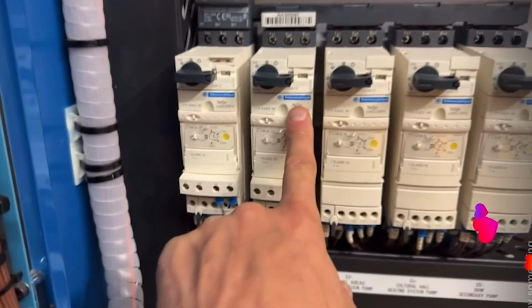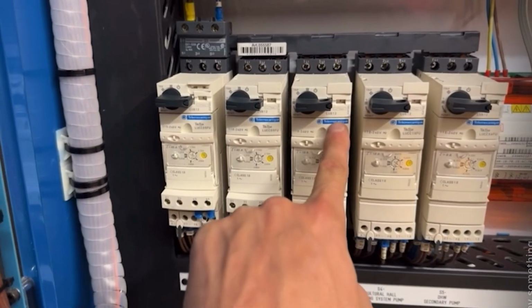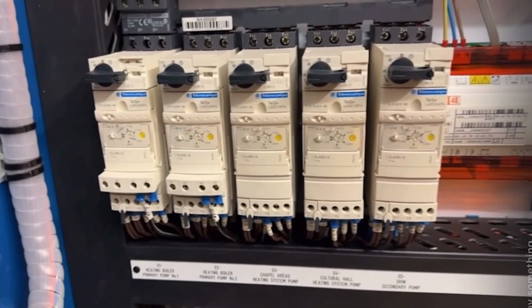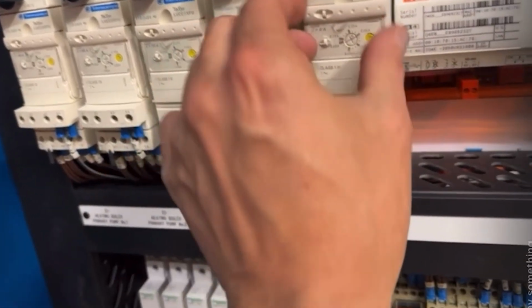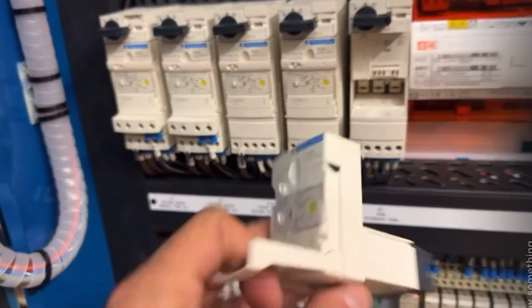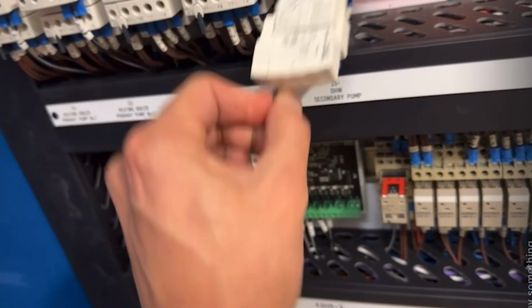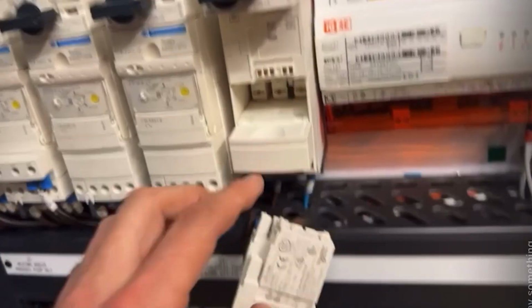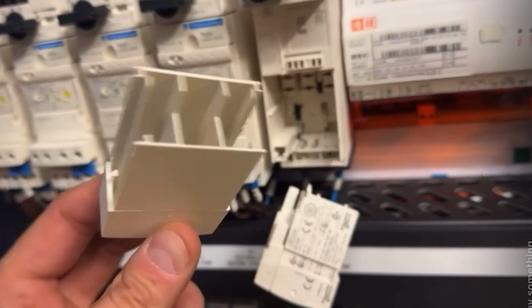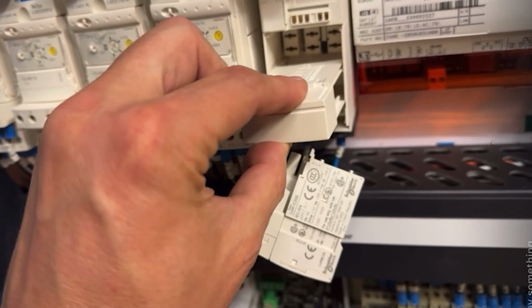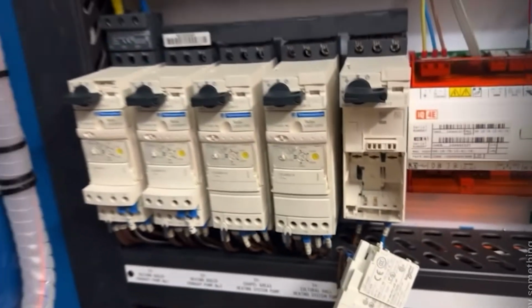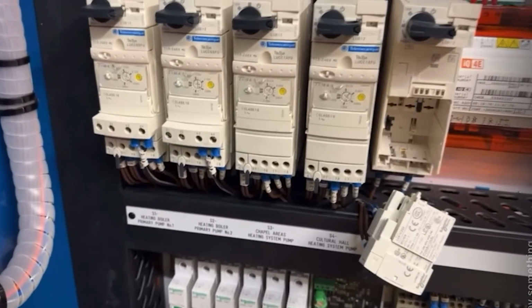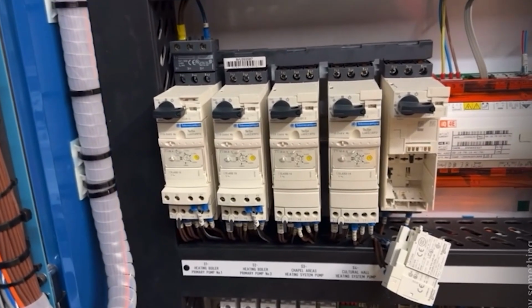This is how I know they're not original, because they say Schneider and they're way too new. These say Telemecanique, which dates them to about 20 years ago, because Telemecanique was bought by Schneider. Also these are pimp because they're modular. That is the overload section, this is the connecting section, and that is a module they sit in where you can put other modules in. I've got a few of these upstairs I can show you. This was a very, very expensive modular system for motor starting, and obviously they've used it in here.